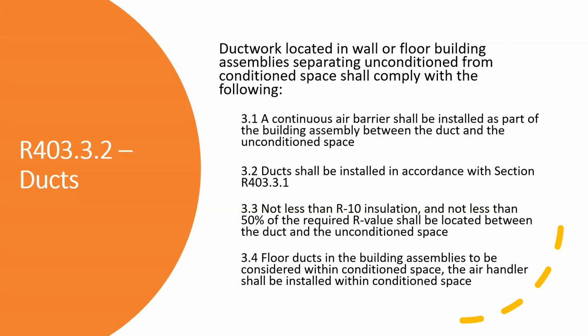Ductwork located in a wall or floor building assembly separating unconditioned from conditioned space shall comply with the following. This is going to bring up a lot of arguments about what is actually intended. But if you're looking at duct chases on an exterior wall, a lot of times those duct chases are built so small that the ducts don't have a lot of room. And in order to make more room, they'll remove the insulation out of the exterior wall, and then they'll put the ductwork directly up against the exterior air barrier. This is calling this out specifically and saying that you have to have insulation between the duct and the outer air barrier. This, in my opinion, also would include, if you read the intent, ductwork laying against roof decking.